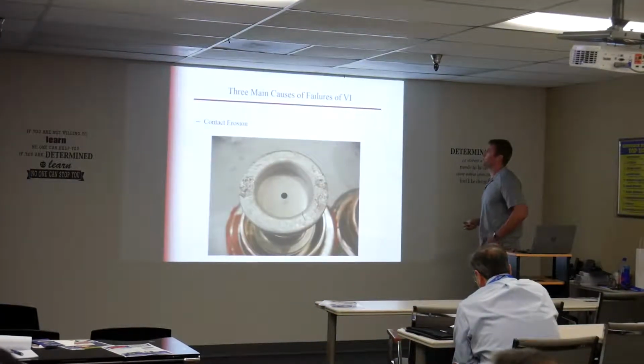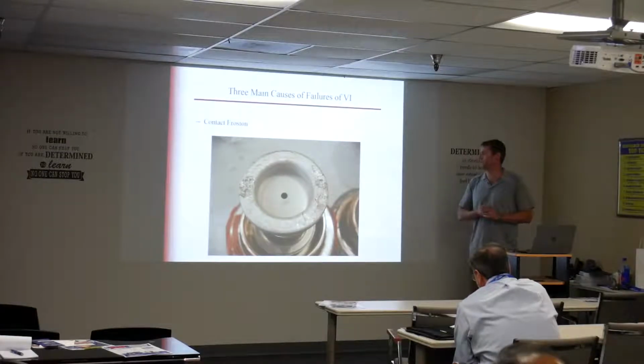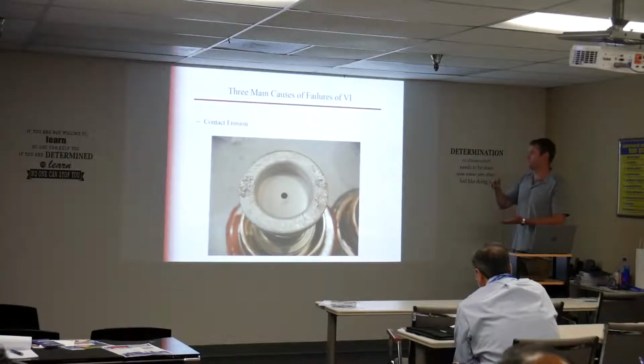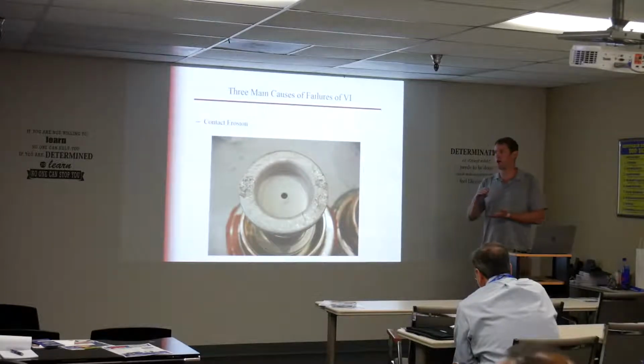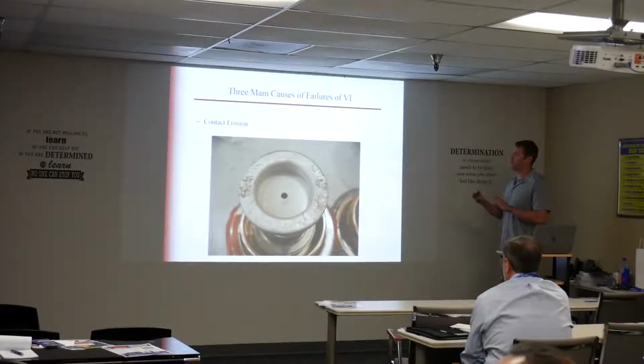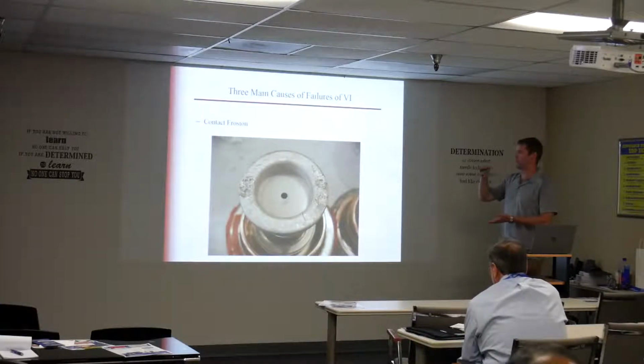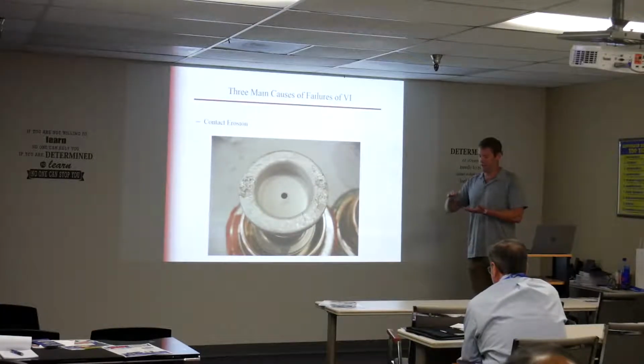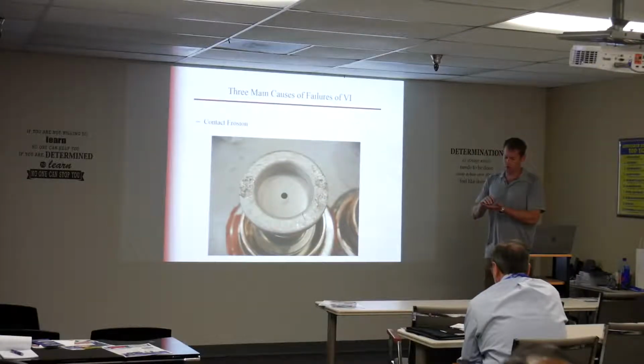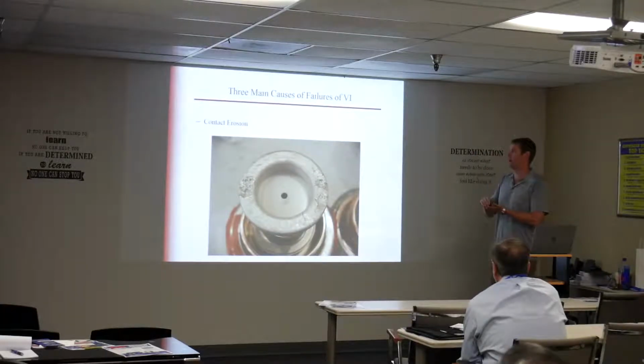So now we go over to the 3 main causes of failures of vacuum interrupters. Number 1 is contact erosion. Like I said, each time you open and close under load, you're drawing an arc, and you're removing a little bit of contact material, so the bottle is actually getting shorter as time goes on. And that's a big deal because when these contacts are closed, there's a lot of electromagnetic force being exerted on them where they're wanting to pop open in service. The contacts are wanting to pop open.